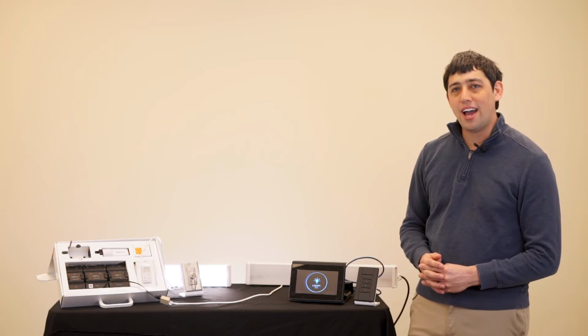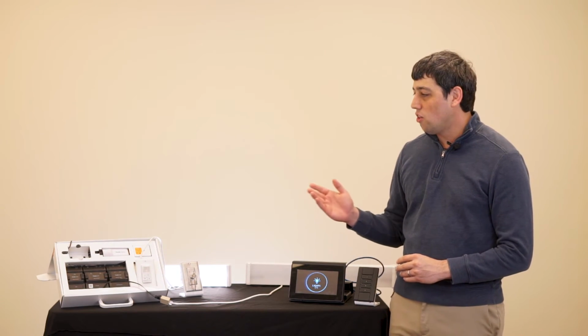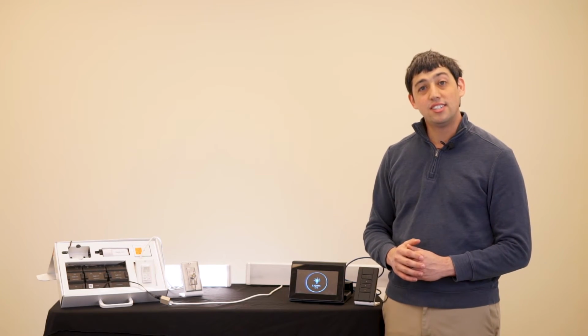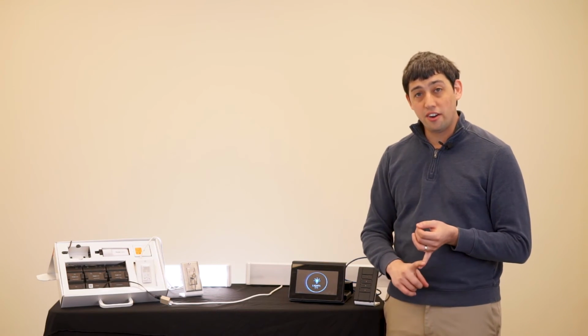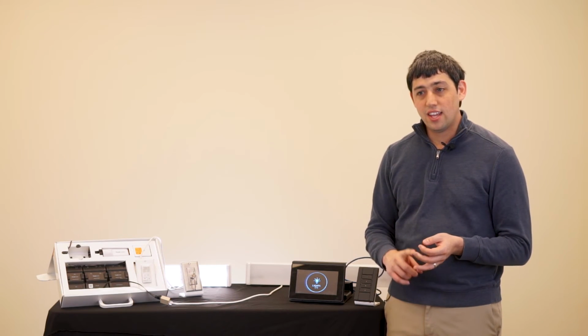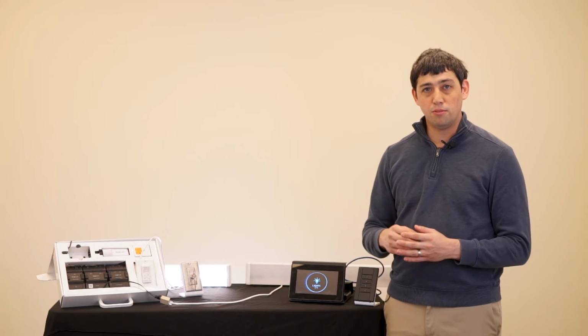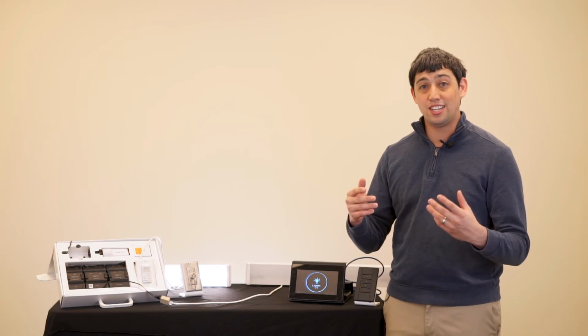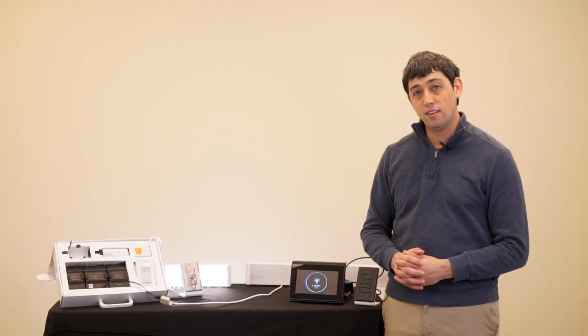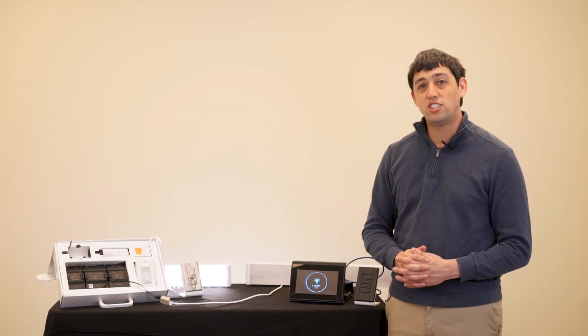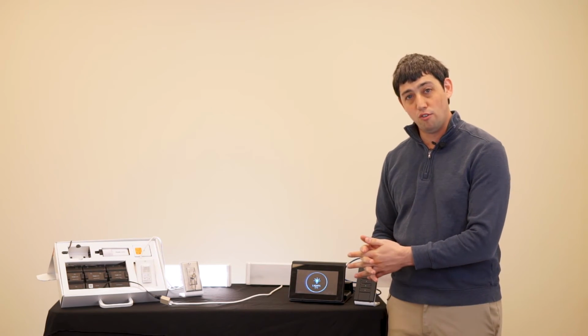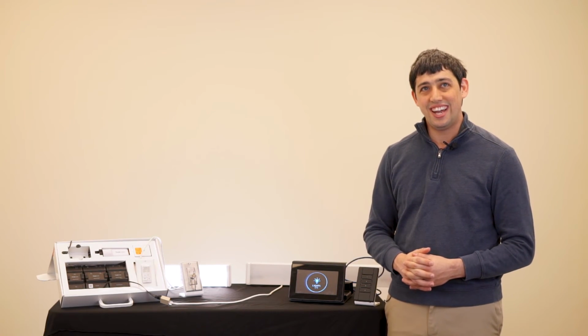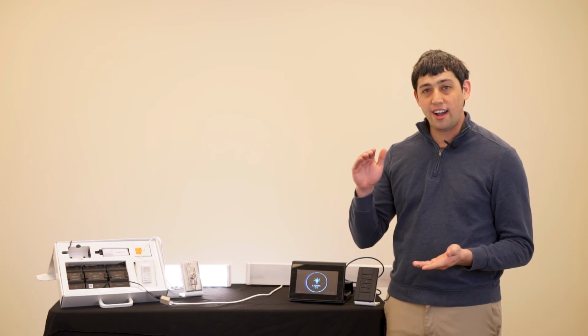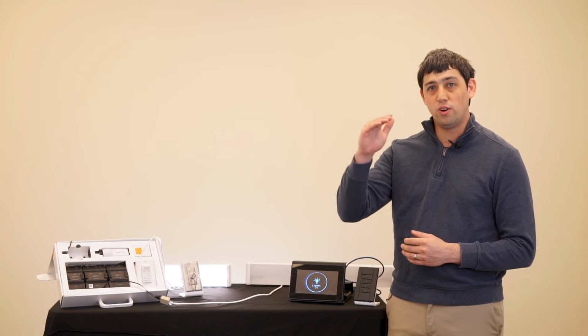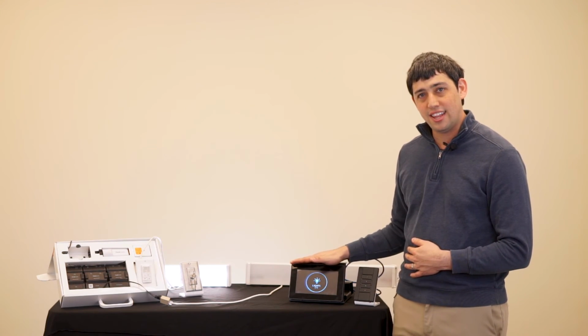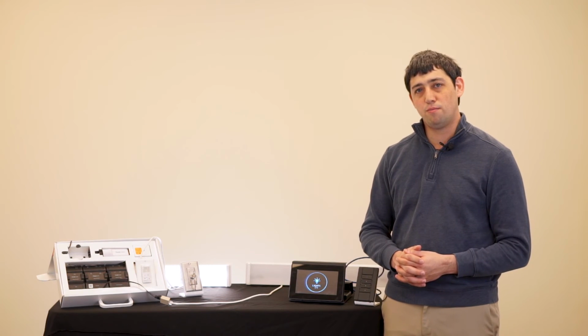The important thing to keep in mind in both cases is all the rules of nLight profiles still apply, looking at priority and also looking at latency. So with nLight profiles, when you set up multiple, you can have different priorities, and the highest priority profile on each device will win. From the Fresco's point of view, it's just tracking the profile in a profile active or profile inactive state. So all of the profiles that the nECY is using to determine which one is highest priority will be active, and that will need to be taken into account in your Fresco programming.